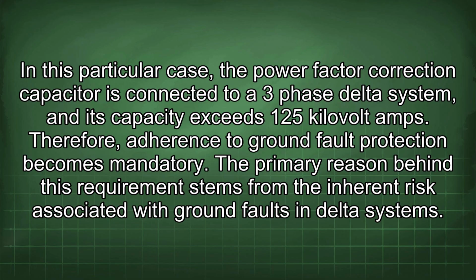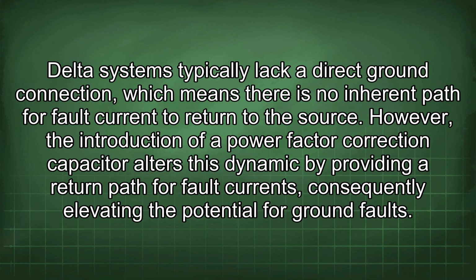In this particular case, the power factor correction capacitor is connected to a three-phase delta system and its capacity exceeds 125 kVA. Therefore, adherence to ground fault protection becomes mandatory. The primary reason behind this requirement stems from the inherent risk associated with ground faults in delta systems. Delta systems typically lack a direct ground connection, which means there is no inherent path for fault current to return to the source. However, the introduction of a power factor correction capacitor alters this dynamic by providing a return path for fault currents, consequently elevating the potential for ground faults.